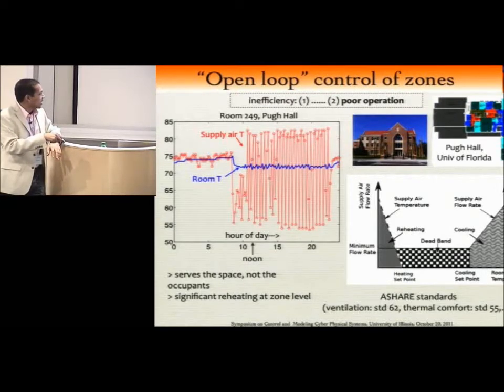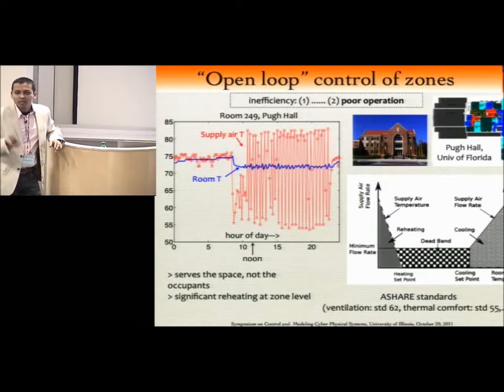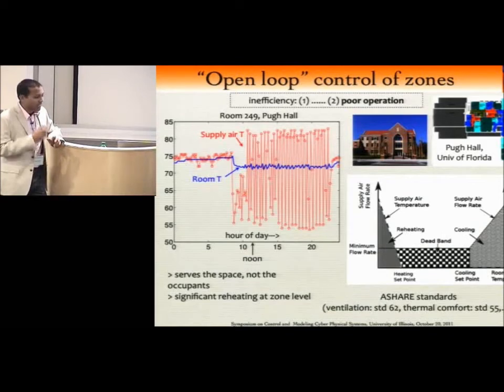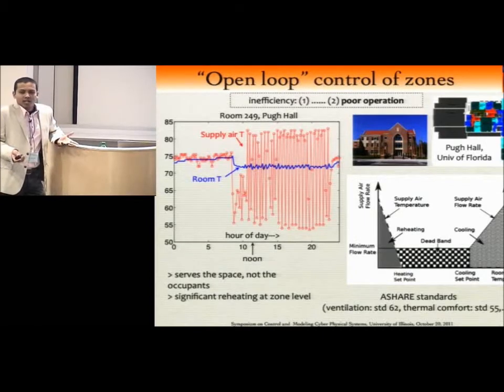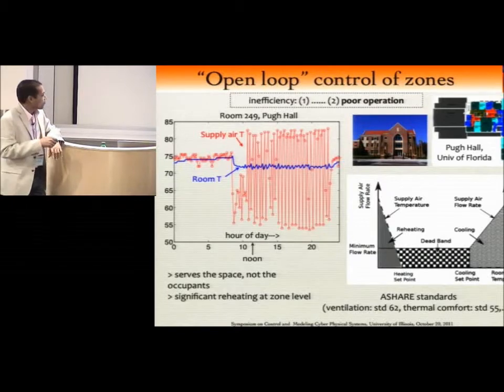The reason it's not allowed to drop the airflow below a certain minimum level is that if it does, then even though temperature might be in the comfortable range, you will not get any fresh air, and that's going to lead to poor indoor air quality. That's actually a much more important variable to control than just temperature. Because if temperature is not right, you will be uncomfortable. That's about it. If indoor air quality is poor, then you'll get sick, and over time the building operator will get slapped with lawsuits. So you don't want that.